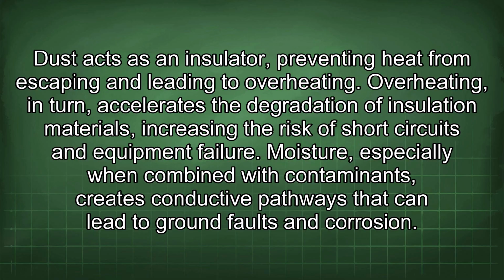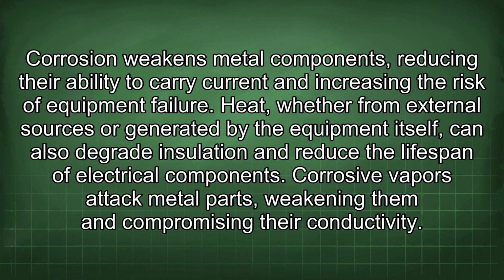Moisture, especially when combined with contaminants, creates conductive pathways that can lead to ground faults and corrosion. Corrosion weakens metal components, reducing their ability to carry current and increasing the risk of equipment failure. Heat, whether from external sources or generated by the equipment itself, can also degrade insulation and reduce the lifespan of electrical components. Corrosive vapors attack metal parts, weakening them and compromising their conductivity.